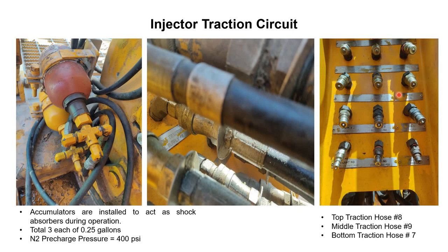Before going ahead, we will see the function of the accumulator in this particular circuit. Accumulators are installed to act as shock absorbers during operation. When we are running in hole or pulling out of hole, there are vibrations in the chains. If these accumulators are not installed, there will be pulsations on the cylinders. To avoid the pulsations, these accumulators are installed. They have pre-charged nitrogen in them and act as shock absorbers.